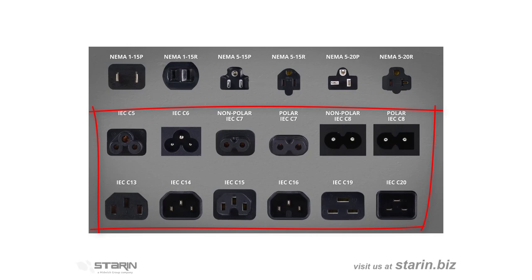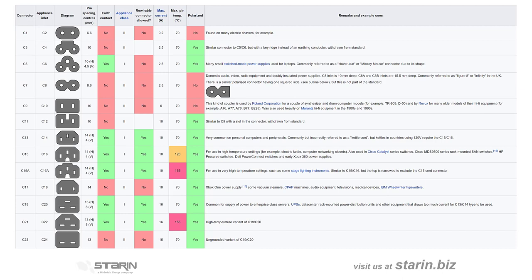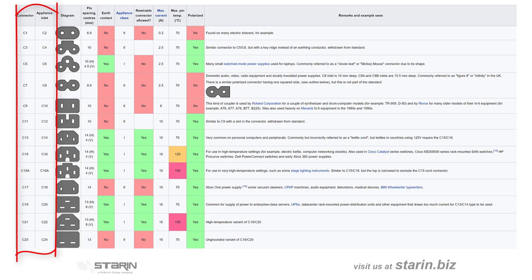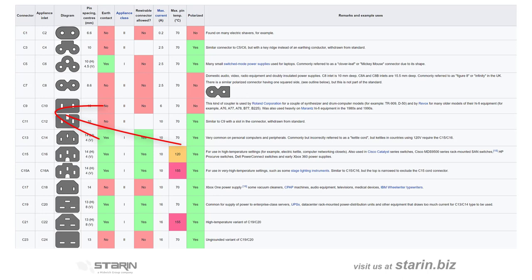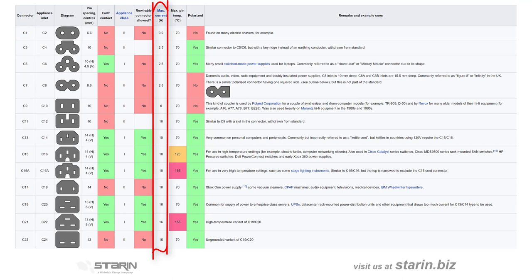When you need to purchase longer, shorter, or replacement power cables for your devices, these are the typical IEC standard connections that you'll need to be able to identify and select. Whether you need a power cable for an external power supply or interfacing to a device with an internal supply, you'll need one of these cables. The point to remember is that the odd numbers are plugs and the even numbers are jacks. Since we typically have a NEMA power plug on one end, the odd numbers are the connectors we usually need. You'll only select the even numbers if you need to replace a power jack on a device. Take note of the current capabilities of these cables — although you have no control over what a manufacturer puts on a device, you should know when a power cable is mismatched for its application.